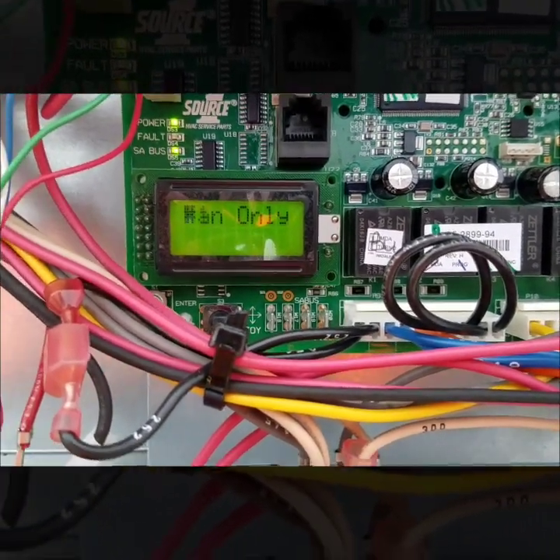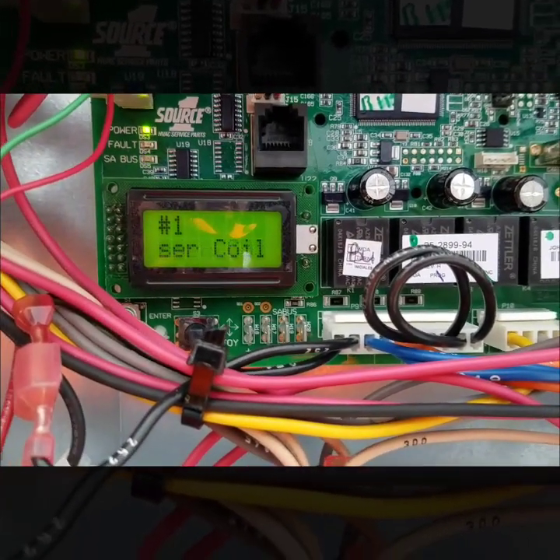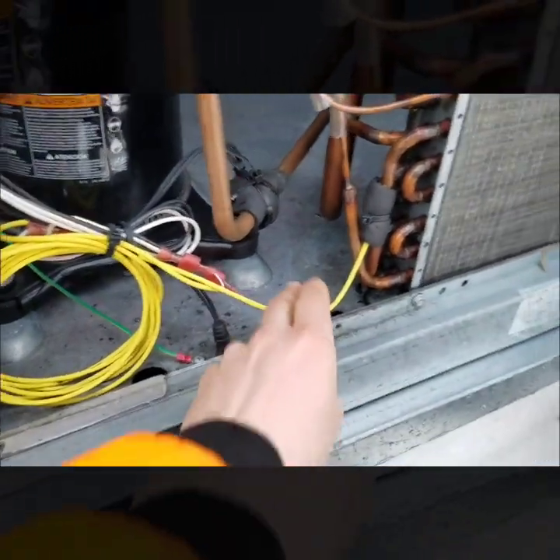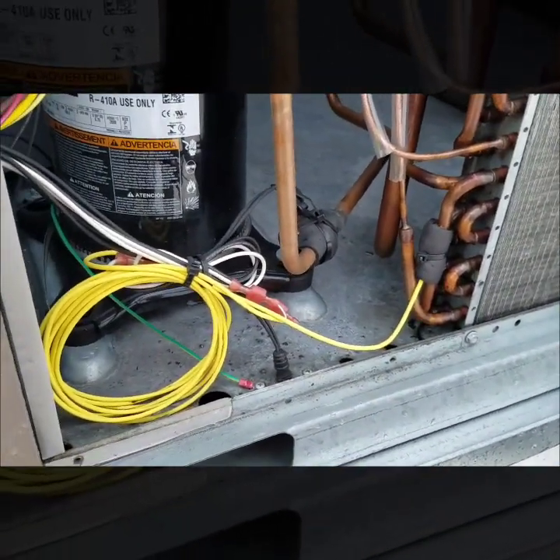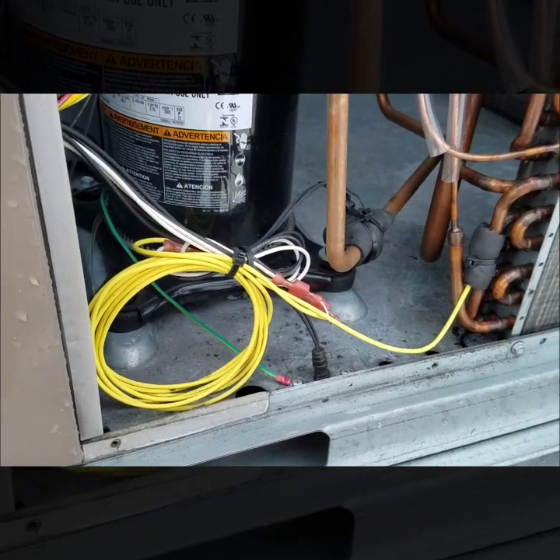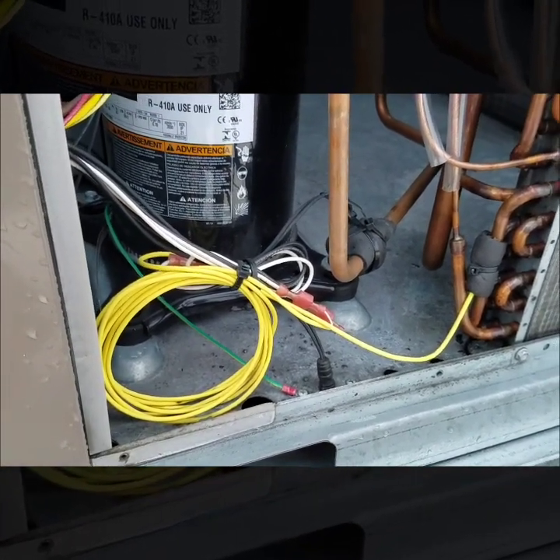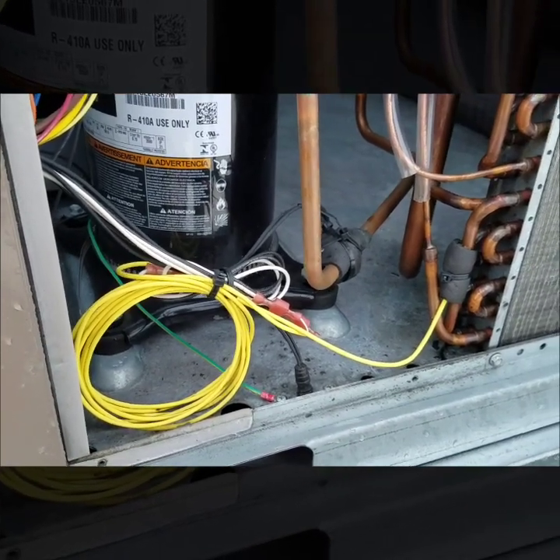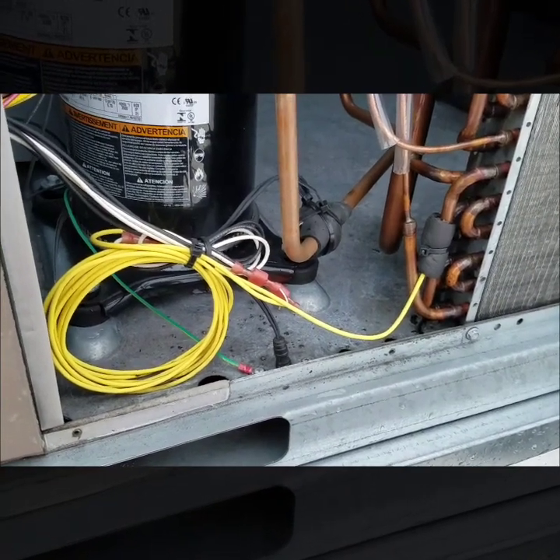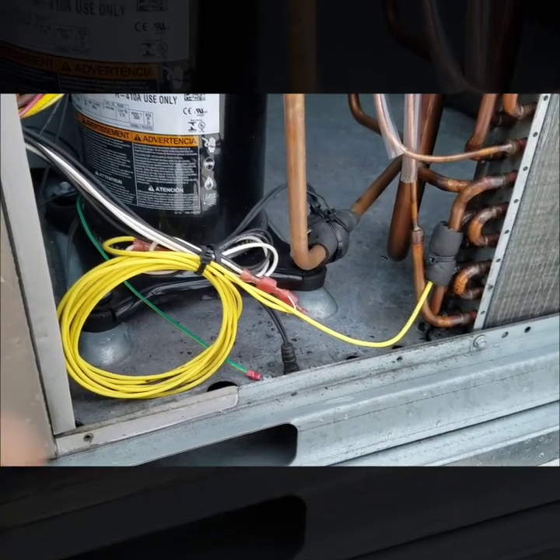I'll cycle back through them here in a sec, but basically you can see a condenser coil sensor, and there's a couple other sensors it was talking about as well. One of them was the ambient outdoor temperature sensor, which you can see right here — this is actually the condenser coil sensor as well.